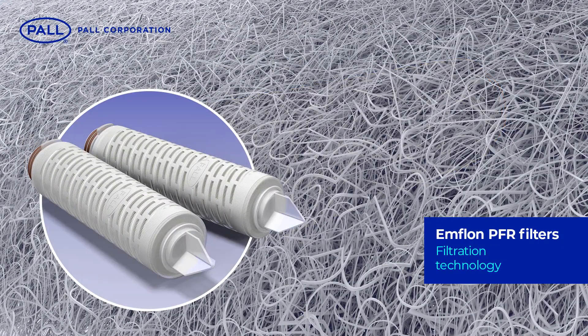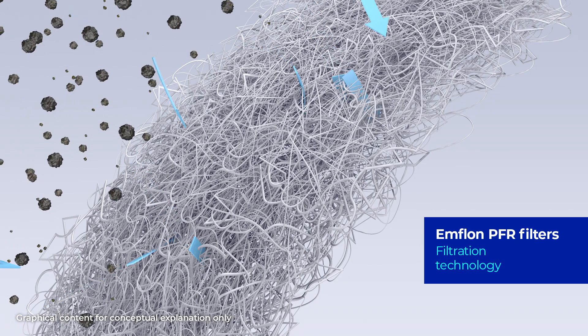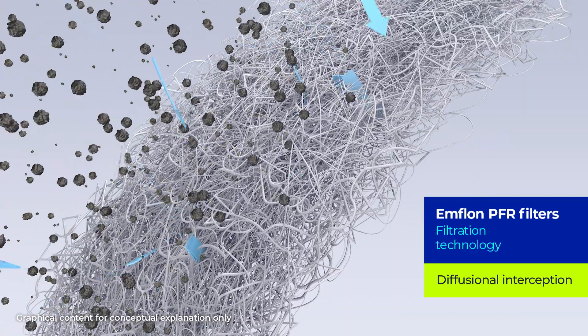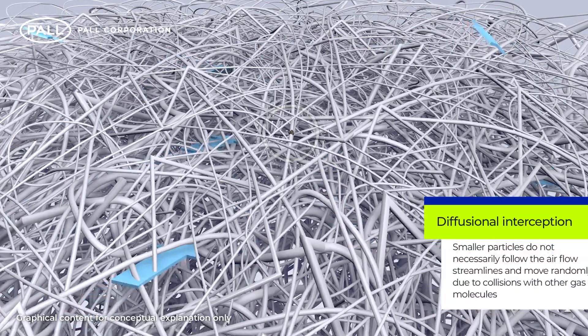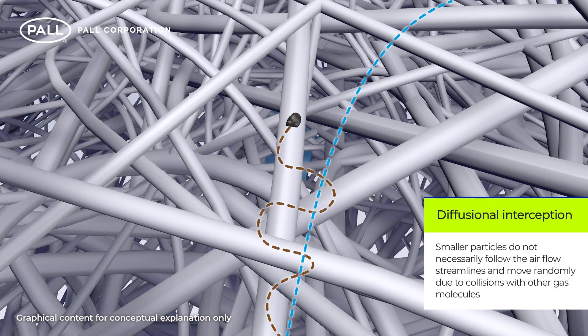The hydrophobic PTFE media used in Emflon filters consists of a sponge-like pore structure. In the case of gas and air applications, these pores use diffusional interception as a method of contaminant removal. Unlike other filtration mechanisms, smaller particles do not necessarily follow the airflow streamlines and move randomly due to collisions with other gas molecules — this is called Brownian motion. The smaller the particle, the higher its freedom of movement and therefore the higher the probability that it will encounter the membrane wall.